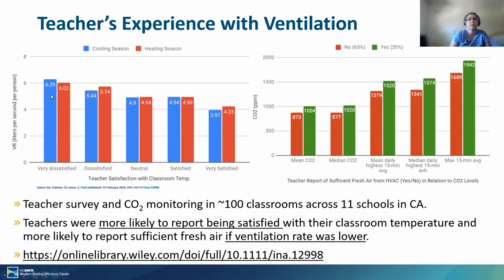If we look at this plot right here, on the y-axis we have the ventilation rate in that classroom, averaged by the teacher's satisfaction with their classroom temperature. The red bar is heating season and the blue bar is cooling season. What you can see here is that satisfaction increased as ventilation rate went down. This is in liters per second per person. All these classrooms on average were underventilated. The California standard would be 7 liters a second per person. This group was close, right? And this group was almost half the ventilation standard.